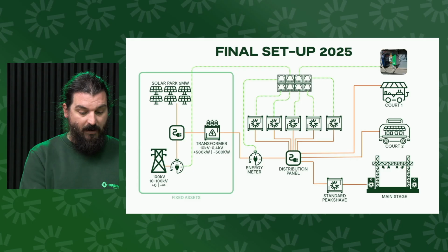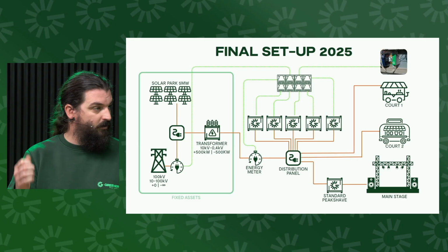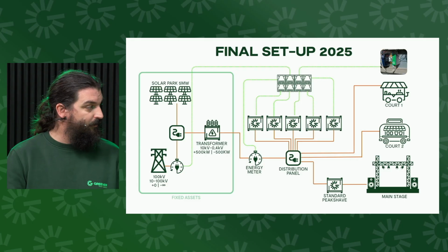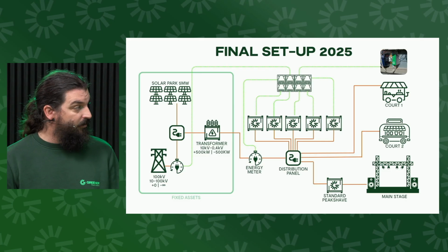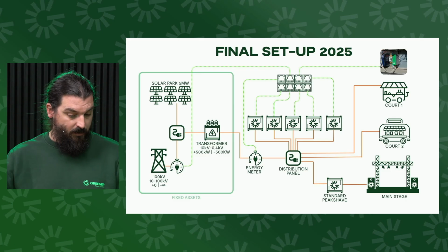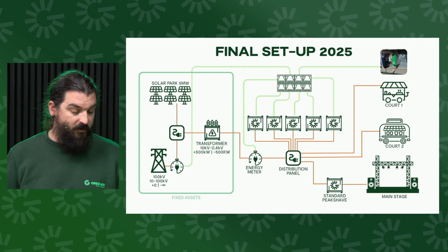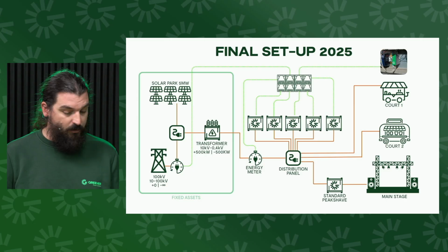And that could also be done remotely. Yes, there will be guys there doing some of the manual switching. There's main switches which need to be done manually, and then the system changing we will be doing. But if it was a permanent installation you were looking to do something similar to this for, you could remotely automate some of that with contactors and motorized breakers. Most transformers do not have a motorized breaker in them as standard.